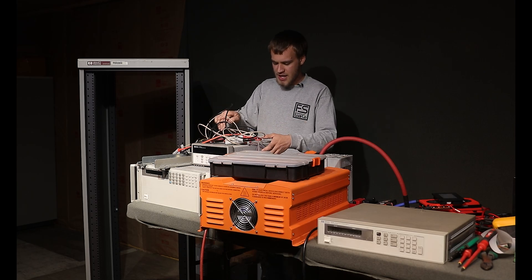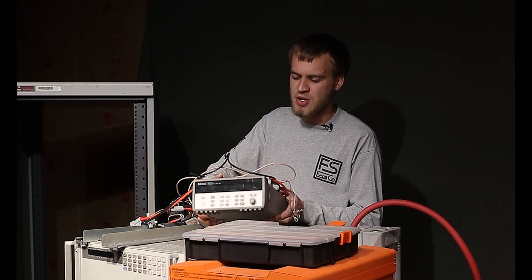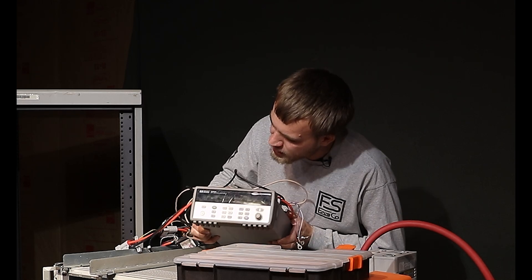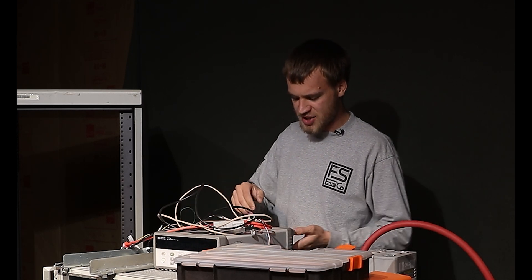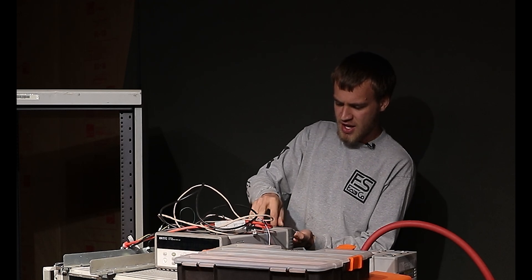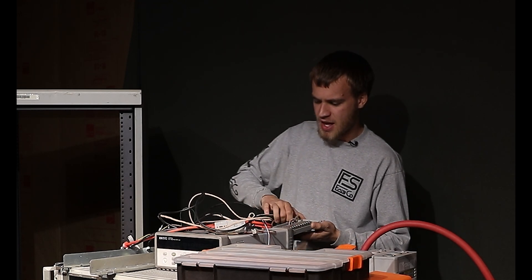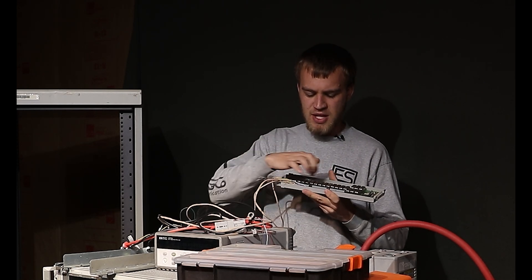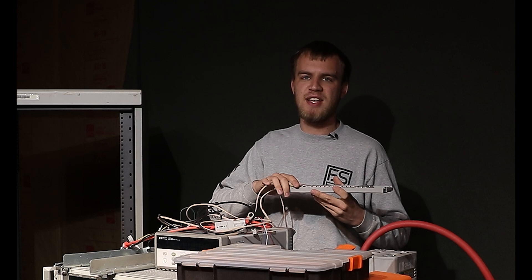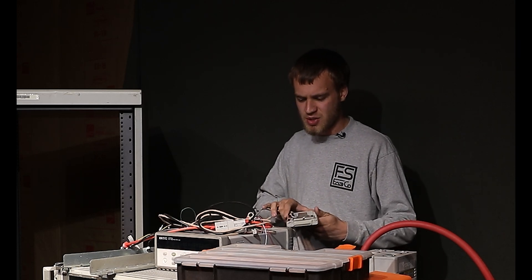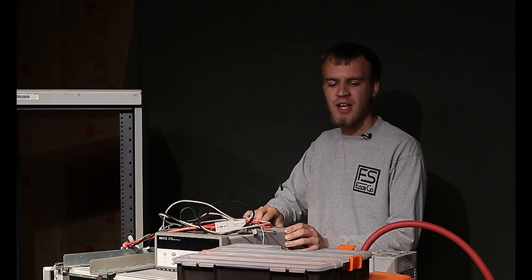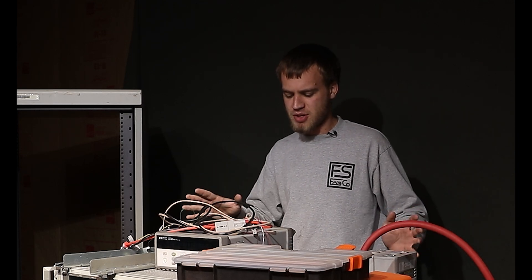And there's a data acquisition unit here. This is a Hewlett Packard, this one is a 34970A. This essentially has cards that go in the back and we'll get some close-ups, but these cards have relays on them and we can select between 16 different sets of high and low pins. So we can use that for individual cell voltage monitoring and a lot of test and measurement stuff here.